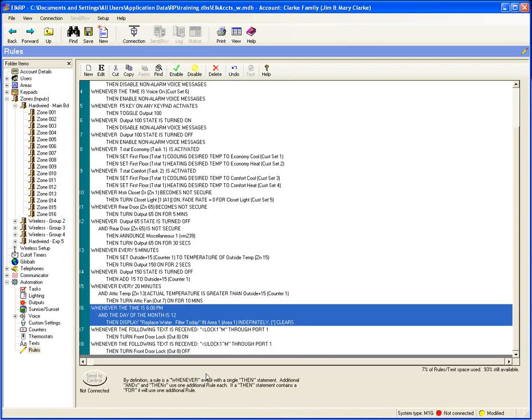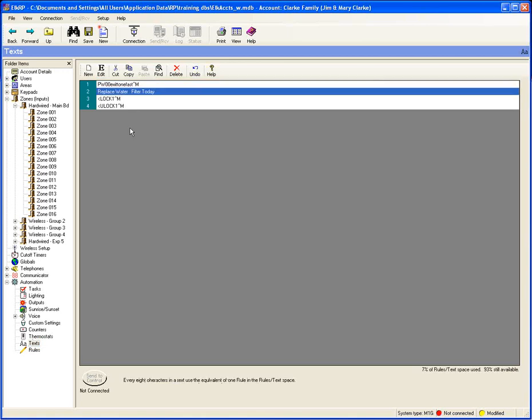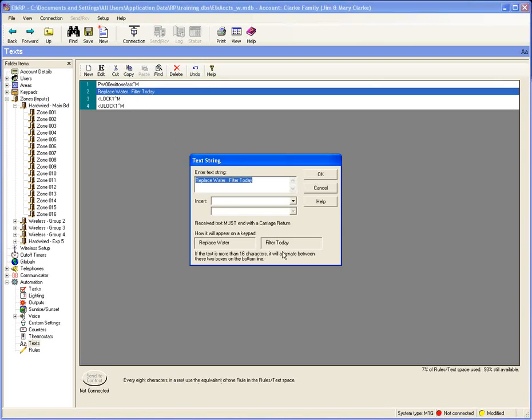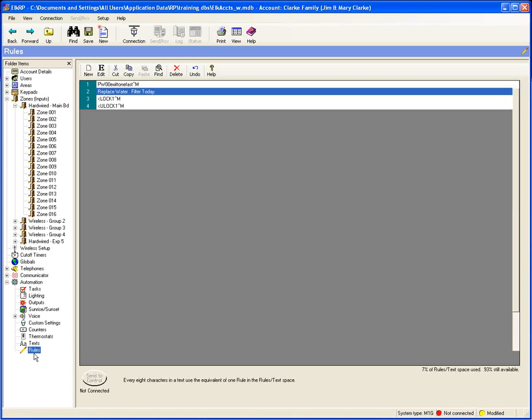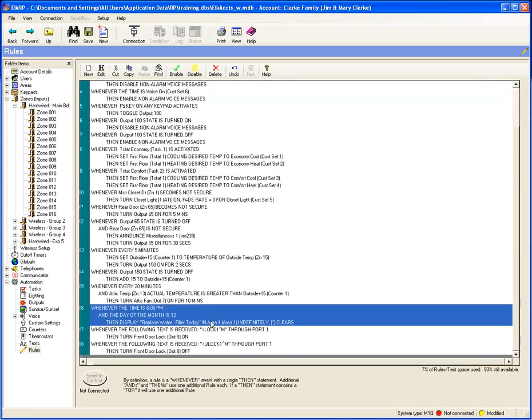Rule number 16 gives a reminder. Under Text, I've set up a message that says 'replace water filter today.' If you take the space out, the text scrolls and gets cut off on the keypad, so the two preview boxes at the bottom show you how it will scroll so you can make adjustments. Set that up under Text, and in rule 16, at 6 PM on the 12th day of every month, it triggers that message.